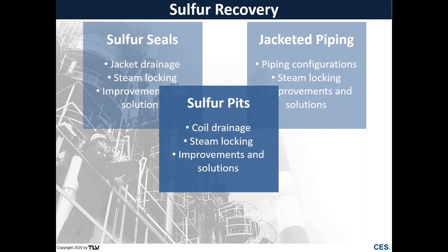So as we look at the next points of our application of sulfur pits, wondering if anybody's starting to see a pattern here. I'll give you a clue. Two words, steam locking. This issue is definitely a major concern in SRUs that we visited all throughout the world.